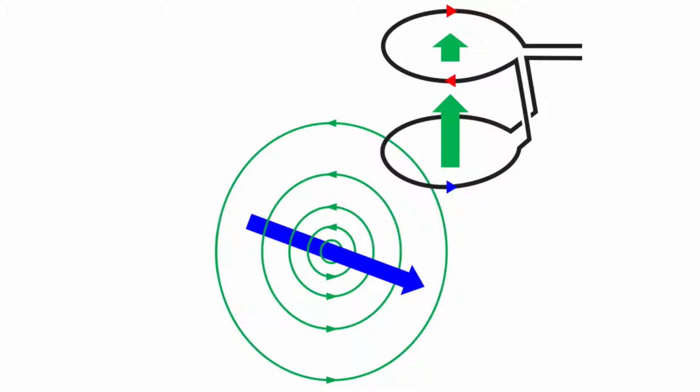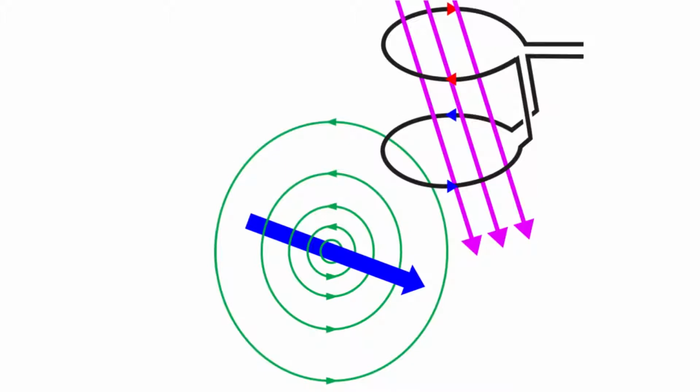In our example, the bottom coil will be most sensitive to the brain, since it is closest to the brain. However, as you can see here in pink, both coils will also pick up ambient noise, which is, in approximation, just as far away from both coils.